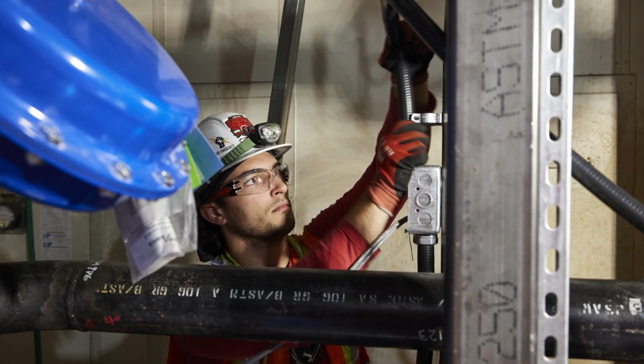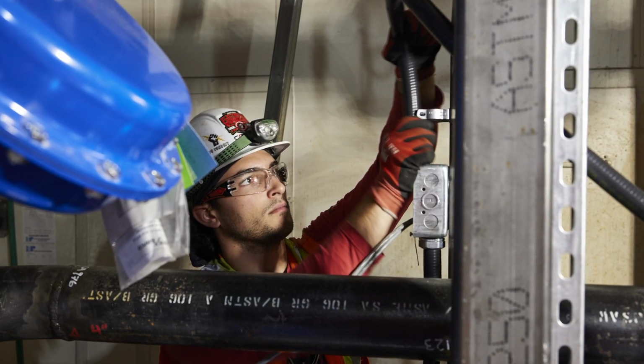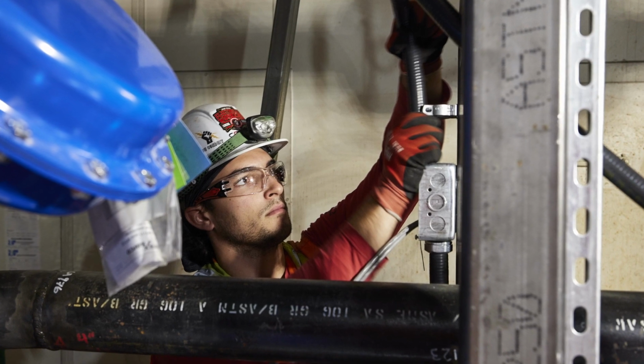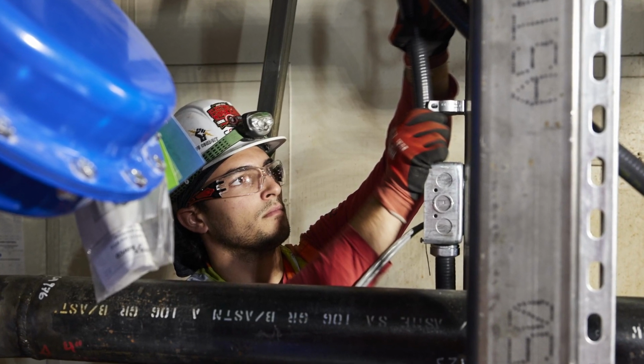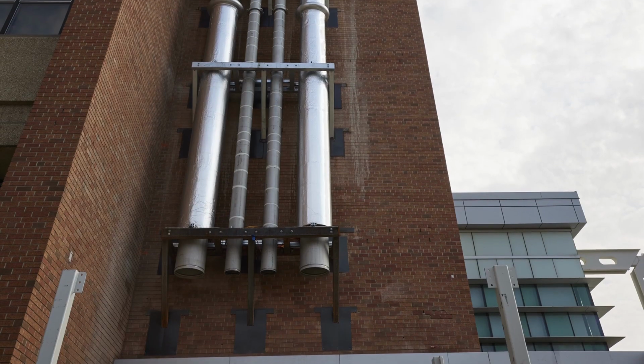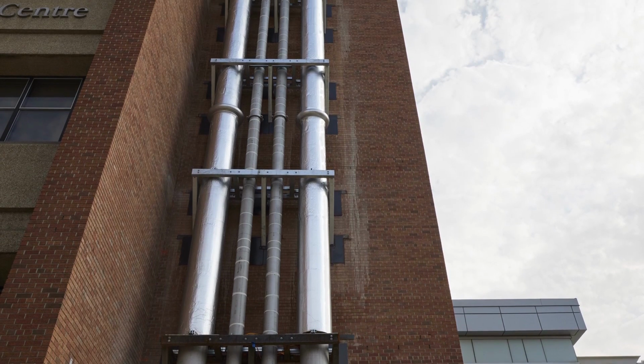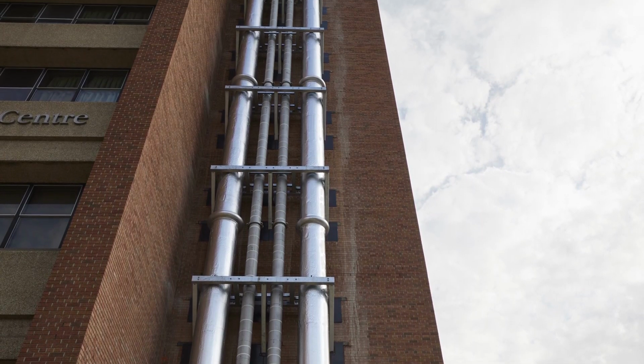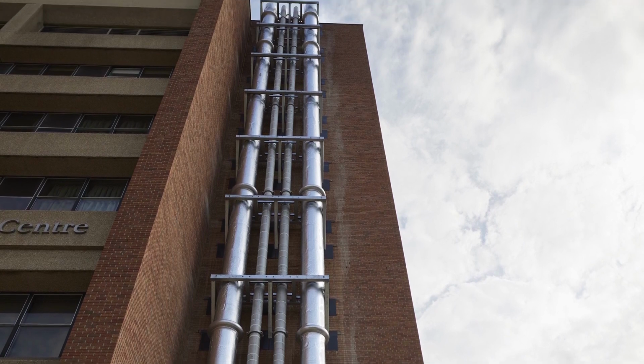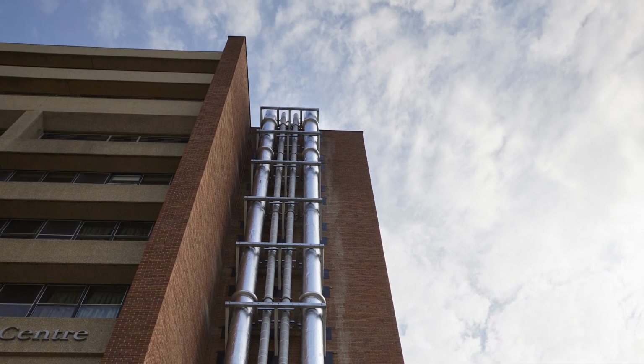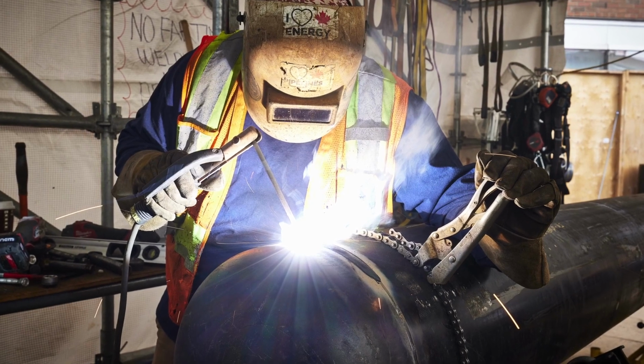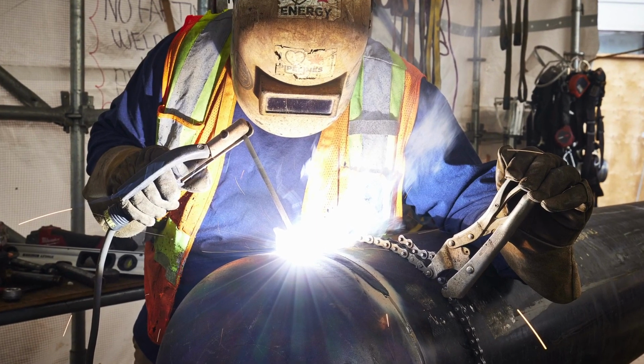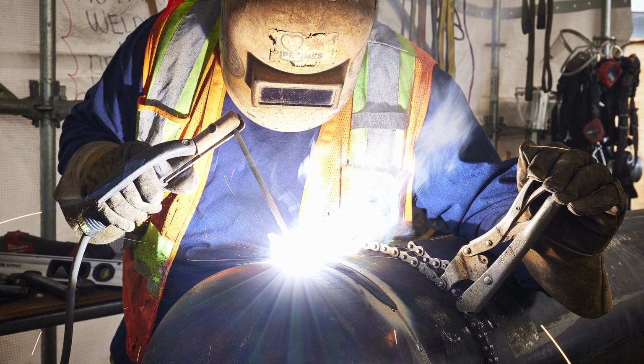Additionally, we worked with the structural engineer to adjust the piping supports to more generic items that generated substantial project savings. One of the major challenges for this project was integrating the new heating system with a hospital that was designed to operate with legacy systems. As the original heating system was done with steam, converting the system to low-temperature hot water posed challenges with replacing infrastructure that was installed in the hospital during the initial build.